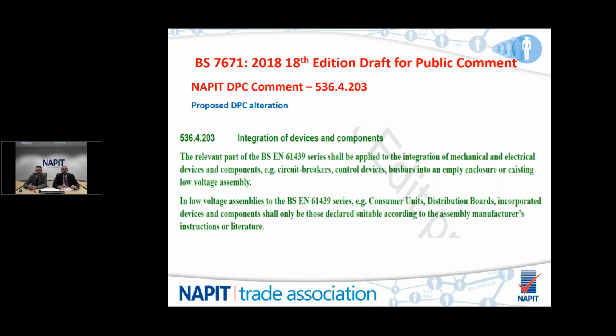Okay, and extremely thought-provoking this one. Integration of devices and components. It's a proposal to ask that, or require that, if you fit equipment into distribution boards, consumer units, enclosures, etc., or similar, the devices you fit in shall only be those declared suitable by that assembly manufacturer's instructions or literature. So what does that mean? Well, if you're going to go and fit a timer, contactor, any types of surge protection device, etc., into a distribution board or consumer unit, it must be made by or declared acceptable by the manufacturer of that enclosure, distribution board or consumer unit.